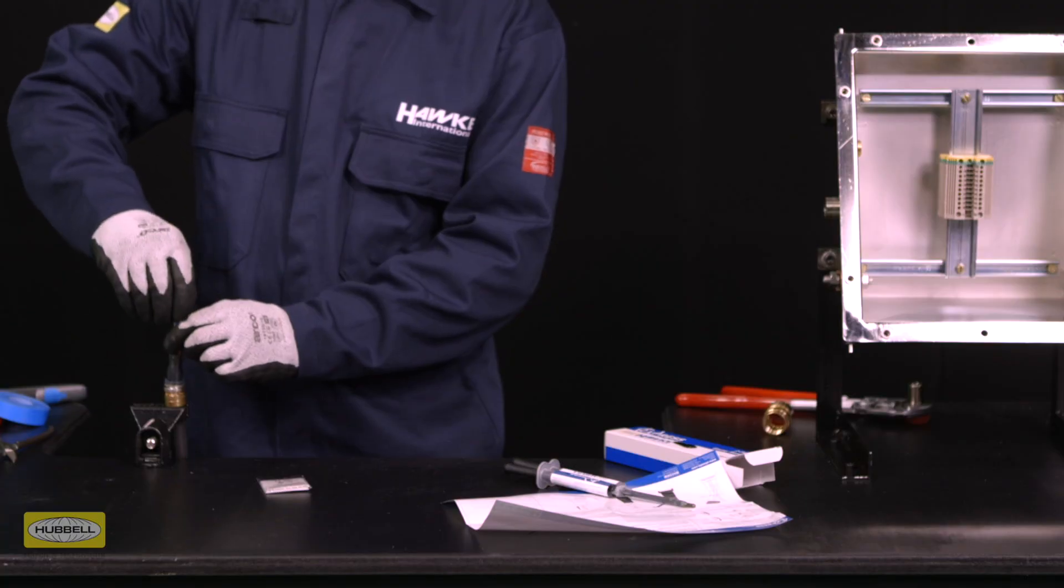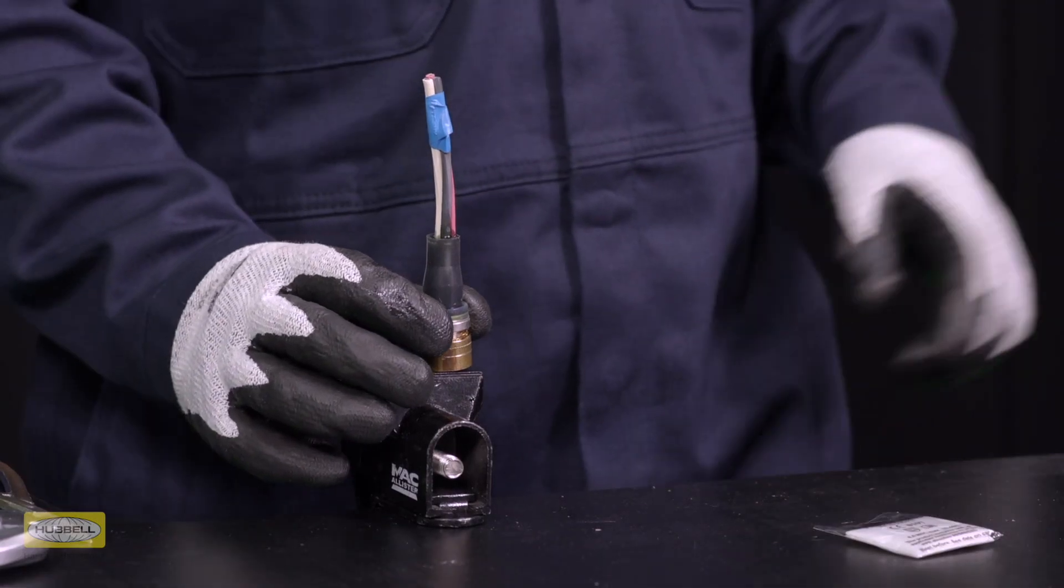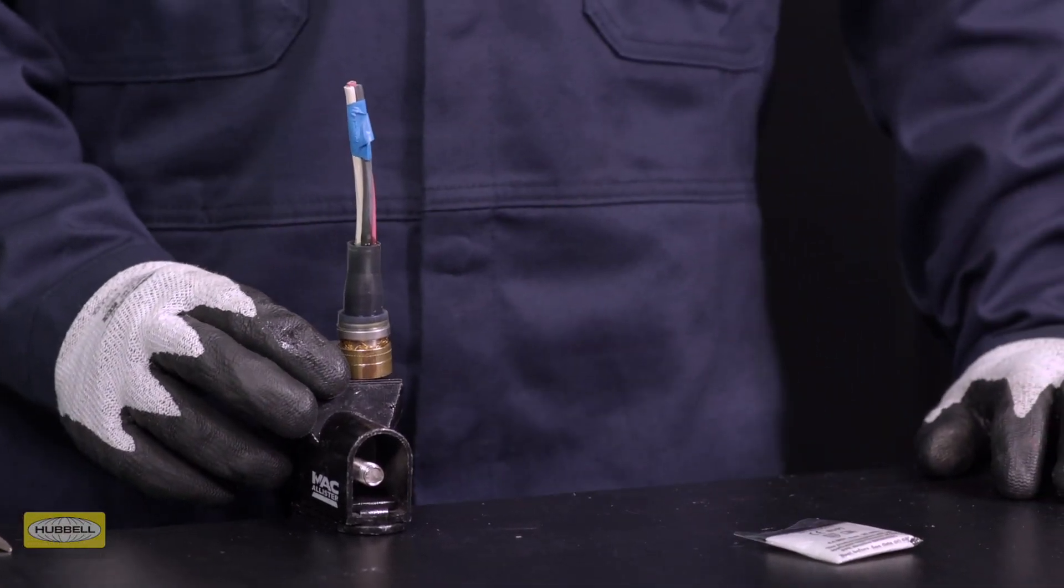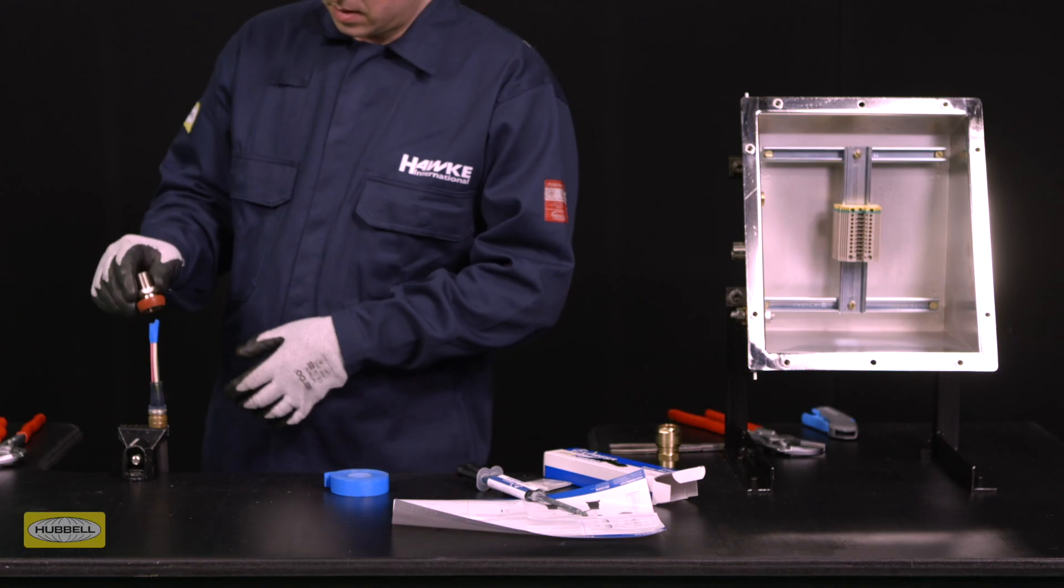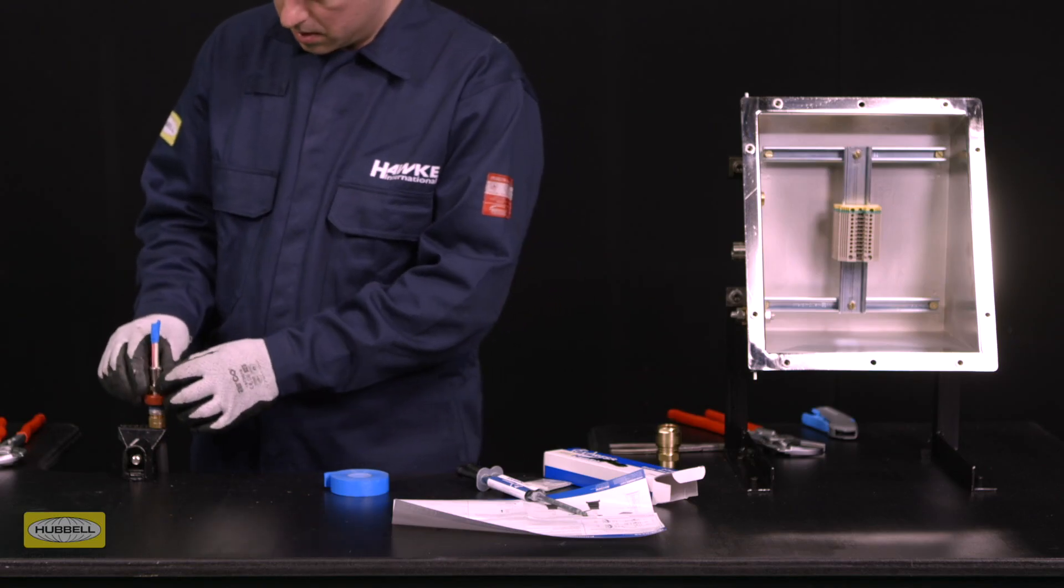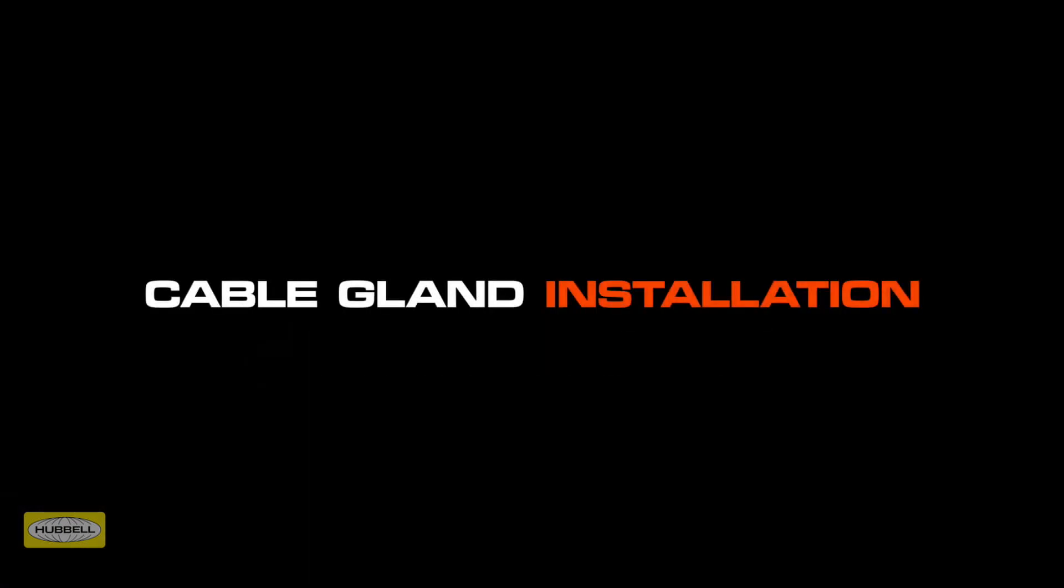Tape the cores so they stand centrally to the pot. If the fill level drops below the minimum level, top up the resin to the fill line. Place the entry over the silicon pot to ensure it is held in the correct position. Gland installation can now continue.